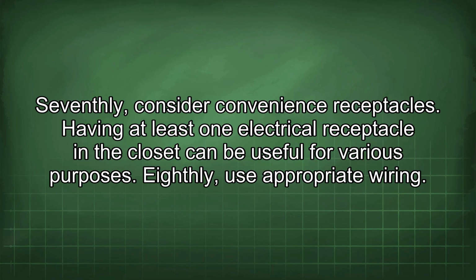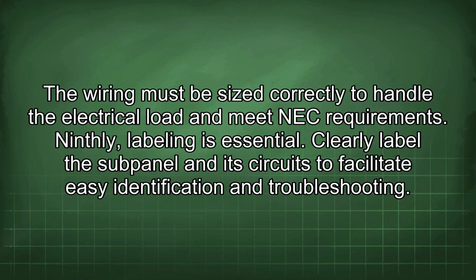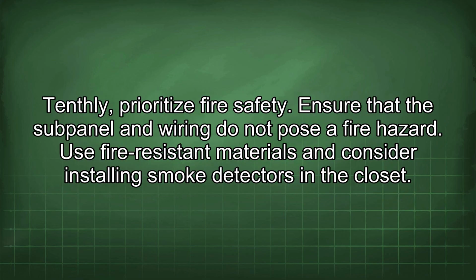Seventhly, consider convenience receptacles. Having at least one electrical receptacle in the closet can be useful for various purposes. Eighthly, use appropriate wiring. The wiring must be sized correctly to handle the electrical load and meet NEC requirements. Ninthly, labeling is essential. Clearly label the subpanel and its circuits to facilitate easy identification and troubleshooting. Tenthly, prioritize fire safety. Ensure that the subpanel and wiring do not pose a fire hazard. Use fire-resistant materials and consider installing smoke detectors in the closet.